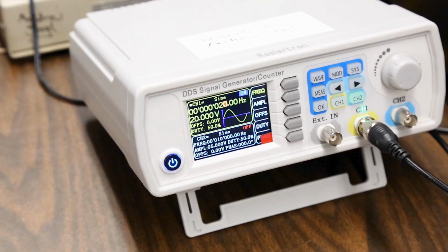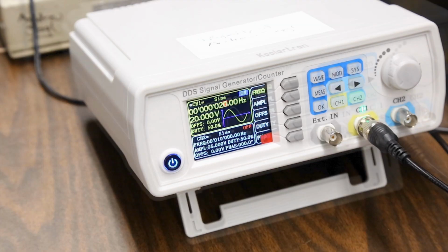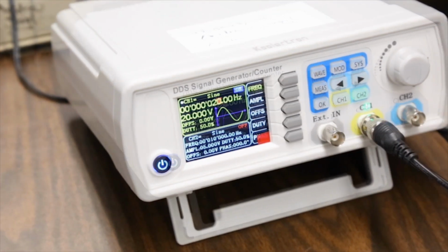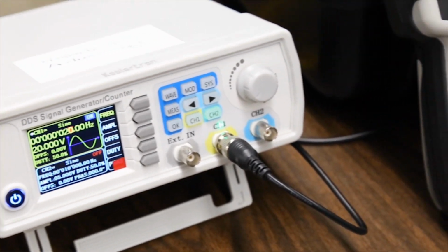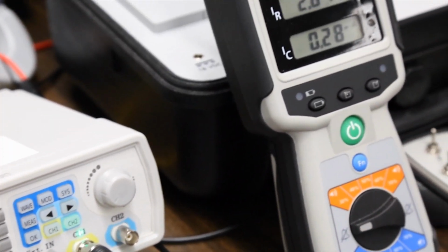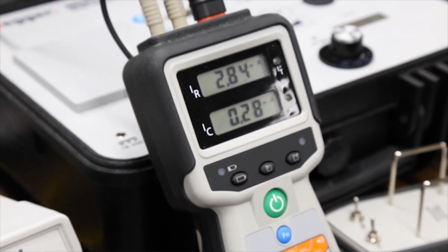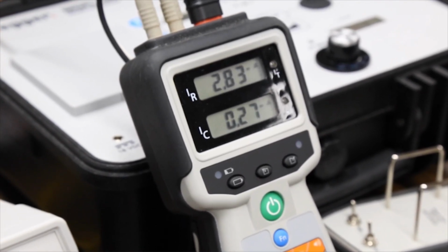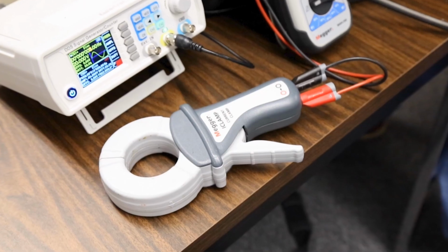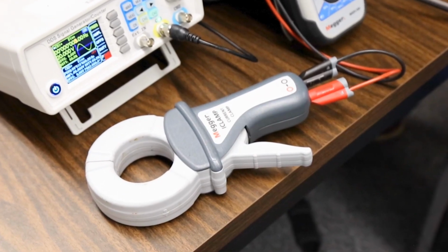Let's look at the effects of low frequency noise on the new Megger MGFL100. We can see at a 20 Hz oscillation, we have a stable measurement. Since the MGFL100 operates at a lower frequency, it is less susceptible to low frequency noise. The MGFL100 is just using one current clamp.